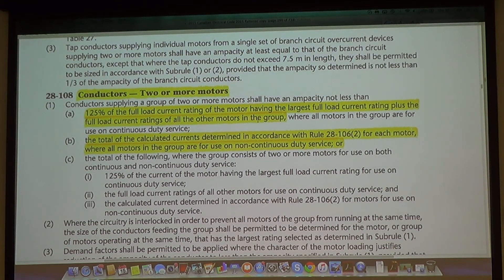Consider them as two questions. Like question number one, where they're all continuous. Question number two, where they're all non-continuous. Let's say first answer is 20 amps, second answer is 60, the total ampacity of the feeder will become 80. You just deal with them separately.